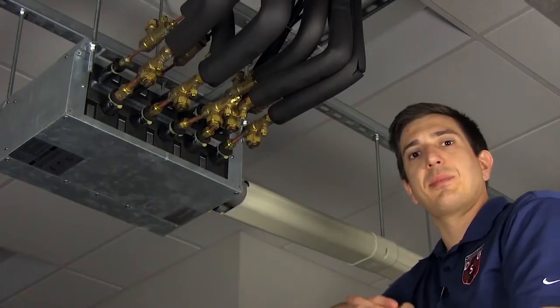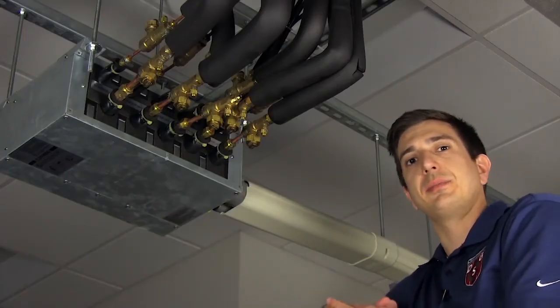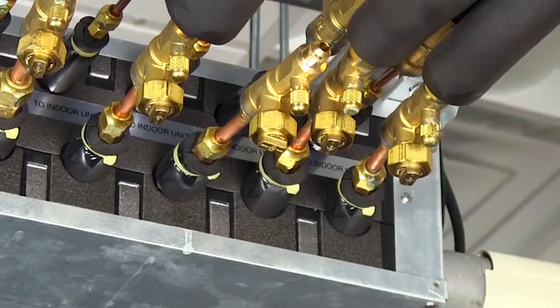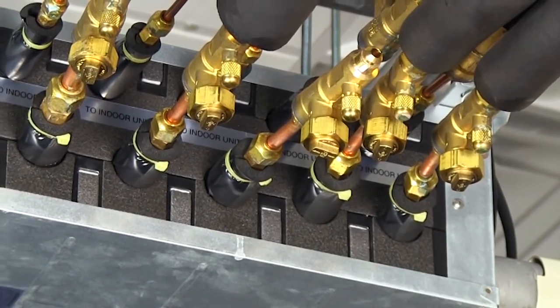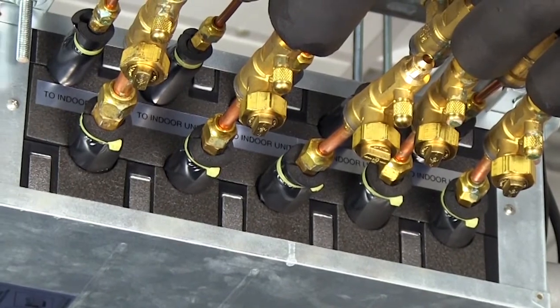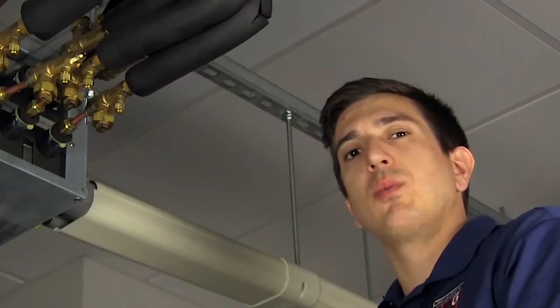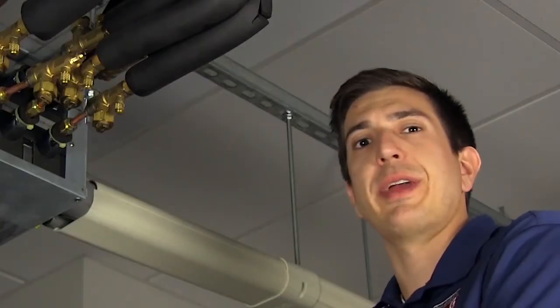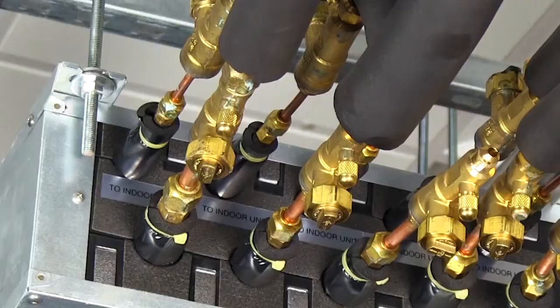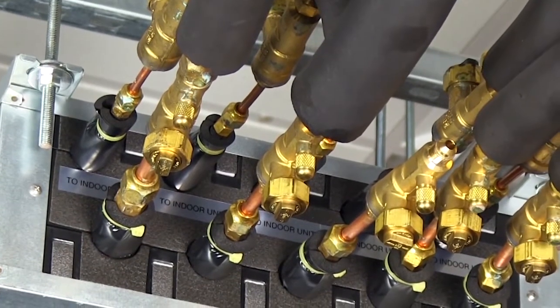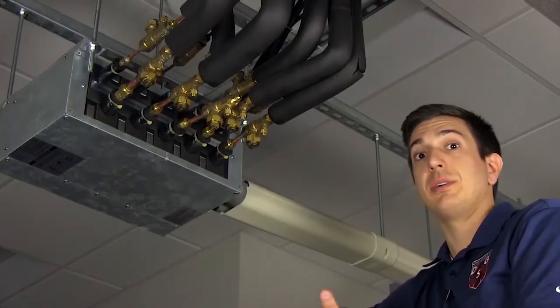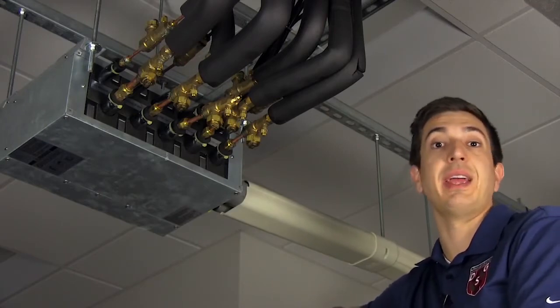In this next example, we're going to be taking a look at a system that's using a branch box. Inside the branch box, there's LEVs, or linear expansion valves, for every zone. What would happen if, say, a linear expansion valve were to be stuck open, constantly flowing refrigerant to the zone, even when it's off? Well, that could lead to a PA error code.